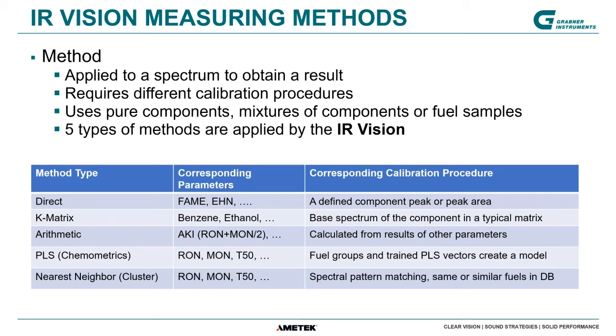Now, we have the spectrum — but how can you get to the corresponding parameters? To get to the parameters I've mentioned — concentrations, octane ratings, and so on — we apply five different types of methods in the IR Vision. We differentiate direct methods, K matrix, arithmetic methods, then chemometrics with partial least squares, and cluster analysis or nearest neighbor search. The corresponding parameters are pure component concentrations for the direct or K matrix methods; arithmetic combinations for the arithmetic method; and property predictions for the PLS chemometrics method.